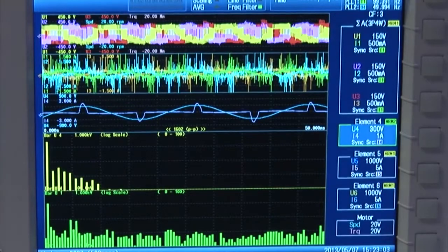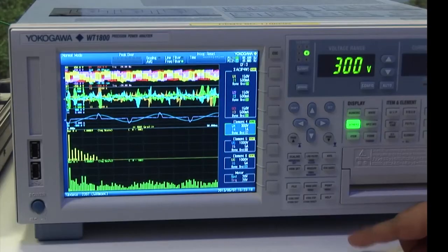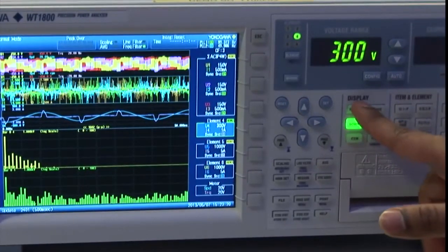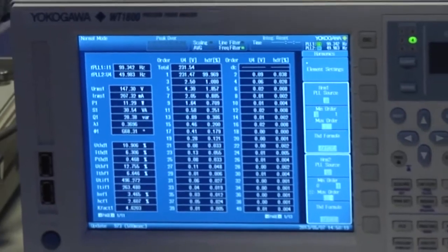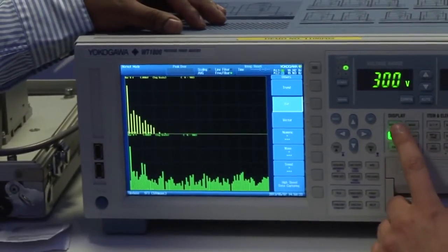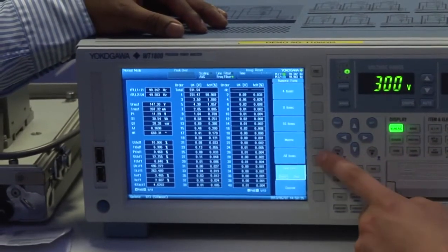In order to minimise the harmonics and increase the power quality, it is important to measure the input and the output harmonic components of the converter. The WT1800's dual harmonic measurement option provides the ability to measure both input and output harmonics simultaneously in one instrument.